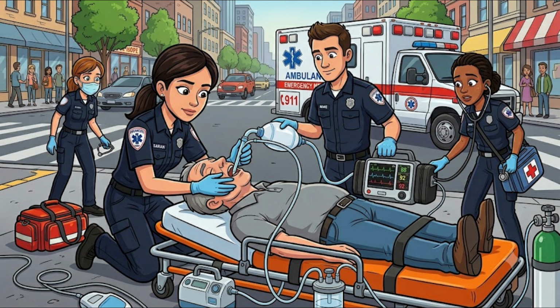Okay, so once the rescuer is protected, the sheet mandates testing the portable unit. You power it on, kink the tubing to block the airflow, and watch the pressure gauge. The protocol requires the machine to hit a minimum of 300 millimeters of mercury. Yeah, and we need to contextualize what 300 millimeters of mercury actually represents. It is a measurement of negative pressure. Vacuum power. Right. Blood, heavy mucus, and particulate vomit are incredibly dense, viscous fluids. To pull a dense, heavy liquid up a plastic tube against the downward force of gravity, well, that requires immense raw vacuum power. Right, because if the machine cannot achieve that 300 millimeter threshold, it will merely pull at the fluid weakly. And leave the airway obstructed.